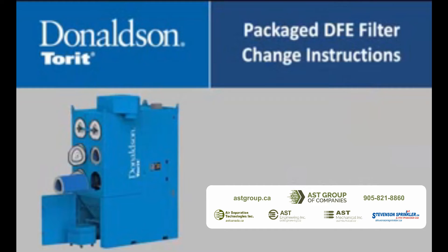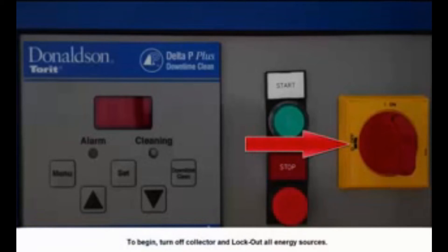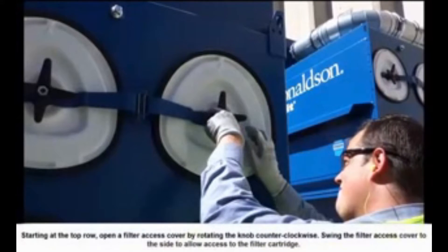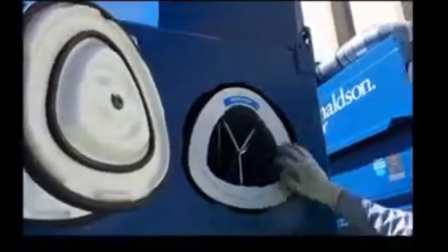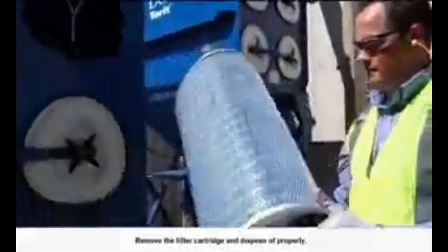The following video highlights the instructions for changing out a filter cartridge on the packaged DFE. To begin, turn off the collector and lock out all energy sources. Starting at the top row, open a filter access cover by rotating the knob counterclockwise. Swing the filter access cover to the side to allow access to the filter cartridge. Slide the exposed filter cartridge out of the access port along the suspension yoke. Remove the filter cartridge and dispose of properly.